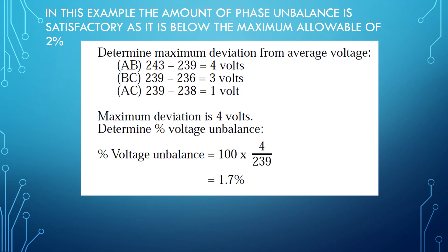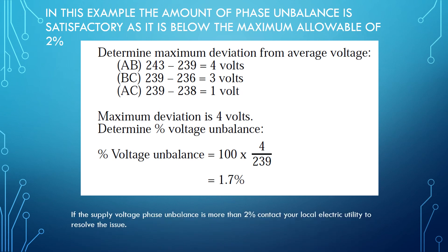Plugging these numbers into the equation of 100 times 4 over 239, we find that our phase unbalance is 1.7%.